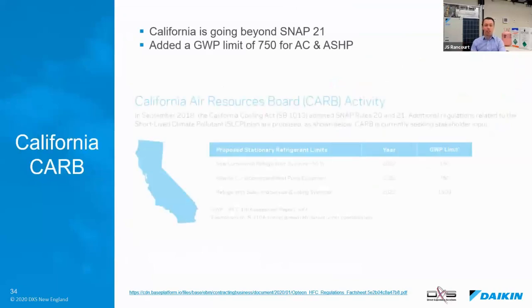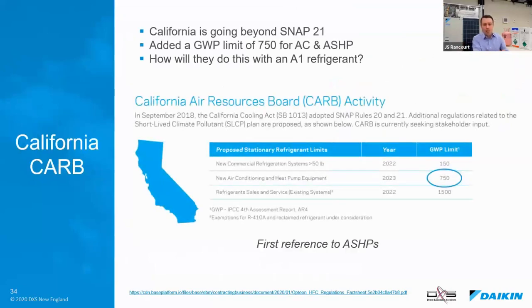Now, California, you might have heard of CARB, which is the California Air Resources Board. California went a step beyond, and they're the first ones to ever introduce a GWP limit on refrigerants for air source heat pumps and air conditioners. This is the first reference to it. Everyone knew that California was going to do this. Everyone's been waiting to see what that number is going to be. Everybody wanted to make sure R32 would fit under that. But still, we're going to talk in a minute about how California is going to achieve this with A1 refrigerants.